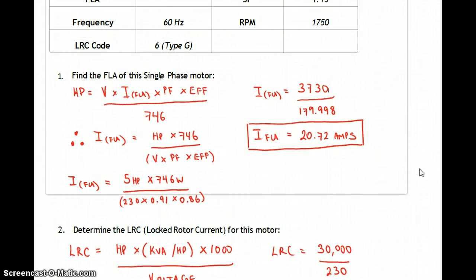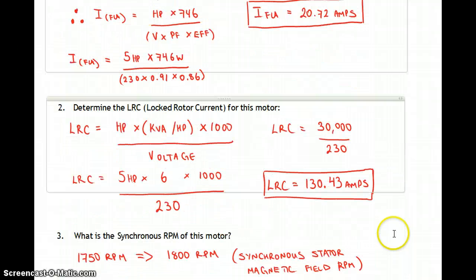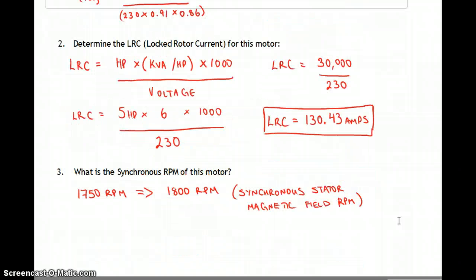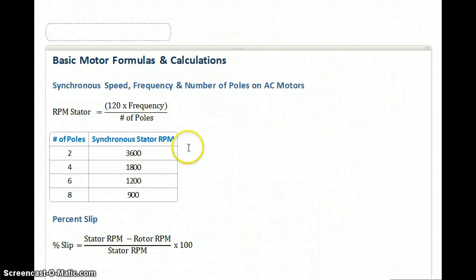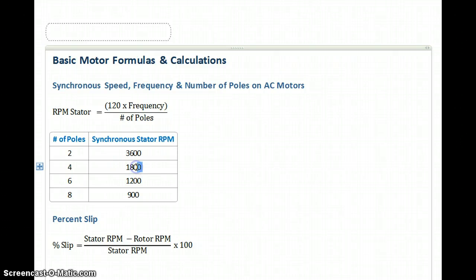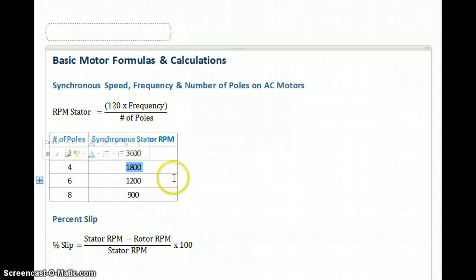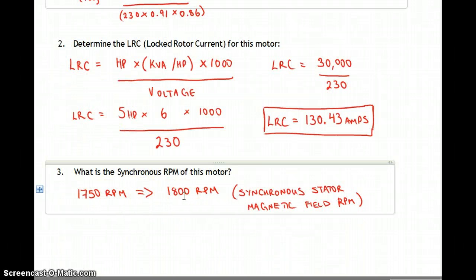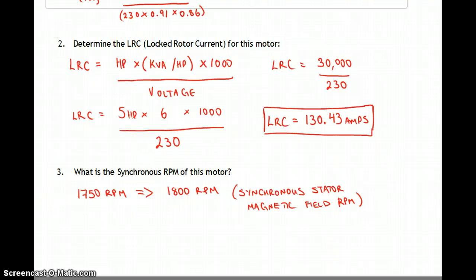Under normal operation this motor pulls 20.7 amps, but at stall or startup it pulls 130.43 amps. For question three, the synchronous RPM: the rotor is 1,750 RPM. Looking at the poles and synchronous speed chart, the closest value is 1,800. So this is a four-pole motor running at 1,800 RPM — that's the synchronous magnetic field speed.